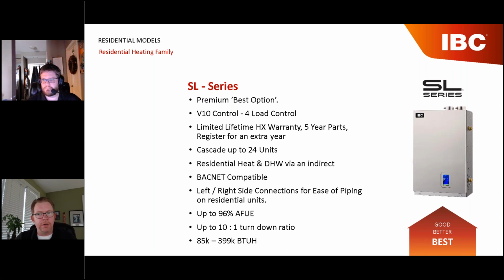You don't get bogged down trying to figure out how to pipe it to avoid phantom flow or BTUs going where they're not supposed to when the indirect is on. A classic example is in the summertime: you've piped it intending to heat the indirect, but you've actually turned the basement into a radiator. With the SL unit, indirect off one side and heating loads off the other, it's a game changer. Big fan.